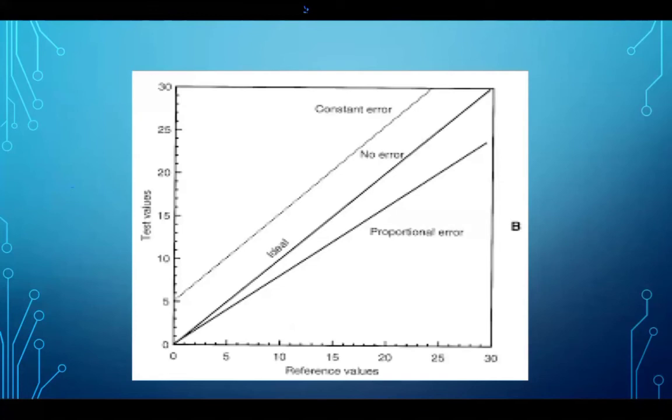And if we want to compare 3-4 machines, which machine is good for us, we can plot these R2 values in a comparison sheet, and we can see B versus A, C versus A, D versus A. These are the different analytes, and we are getting more than say 0.95 R2 value for most of the parameters in this machine C. So that means this machine is good for us.